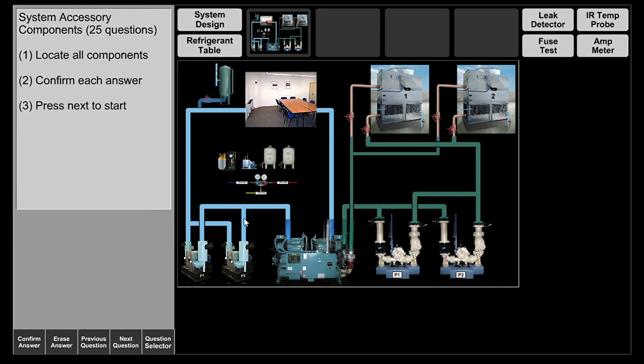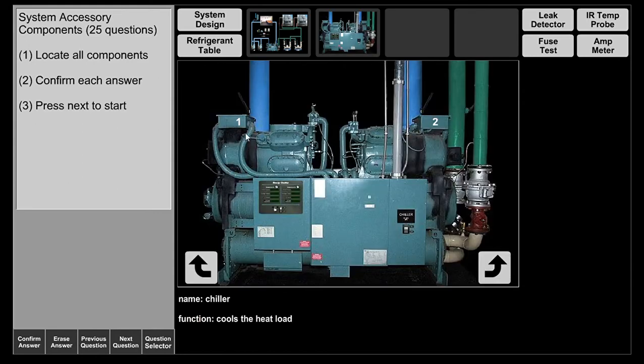The water is still at 55 degrees and we want to bring it down to 45 degrees, so it enters the chiller system — specifically the evaporator. This 55-degree water goes through coils inside the evaporator barrel, and outside the coils you have refrigerant. The refrigerant is a low pressure, low temperature liquid, and as it picks up heat from the 55-degree chilled water it turns into a low pressure, low temperature superheated vapor.